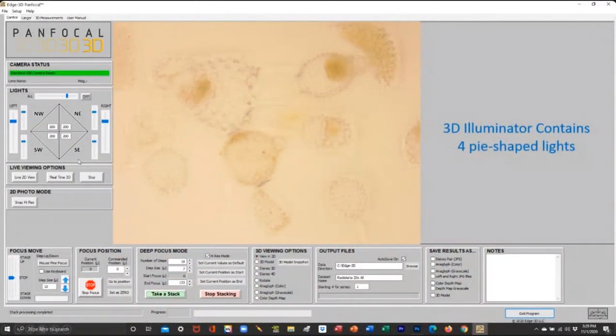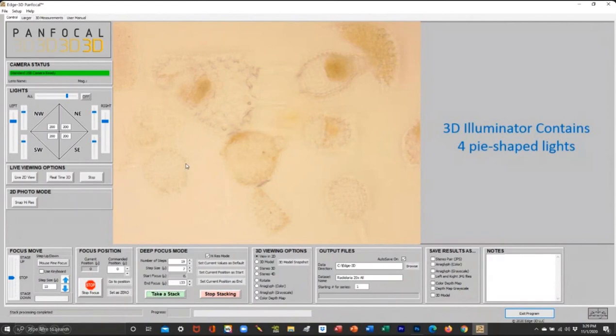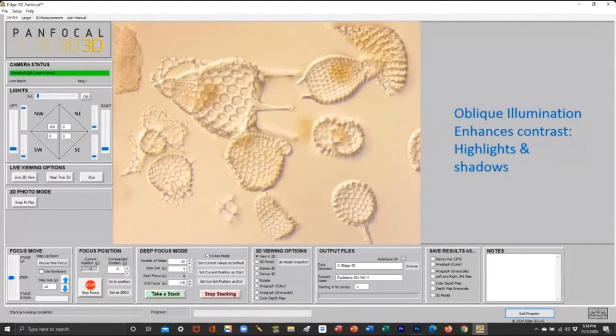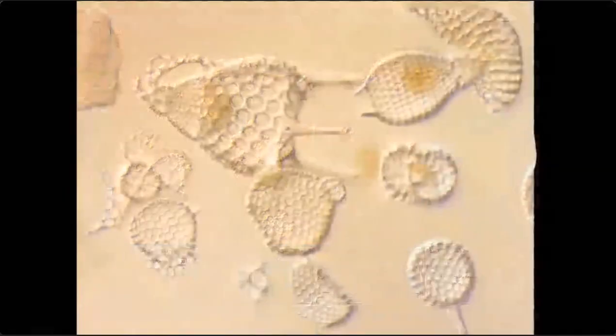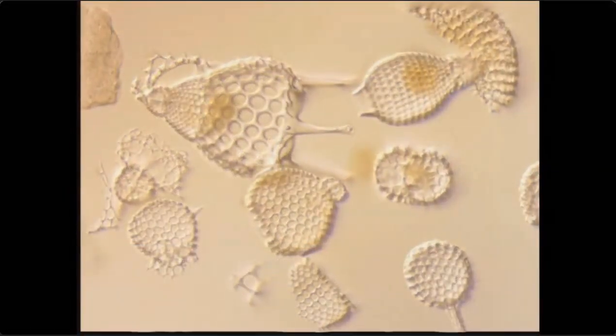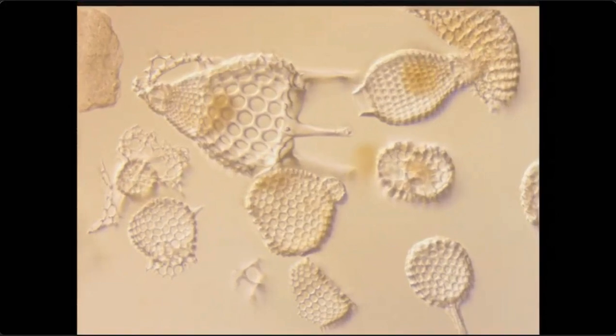On the graphic user interface, the top slider uses all the lights — you can turn all lights on or off, like a standard 2D microscope, and as you slide right they're all ganged together. Now look what happens when we use just the northwest light — all other lights are off — and you can really see what's happening there, it makes a huge difference in visibility. You can also make a 3D rotational movie clip out of it very quickly.